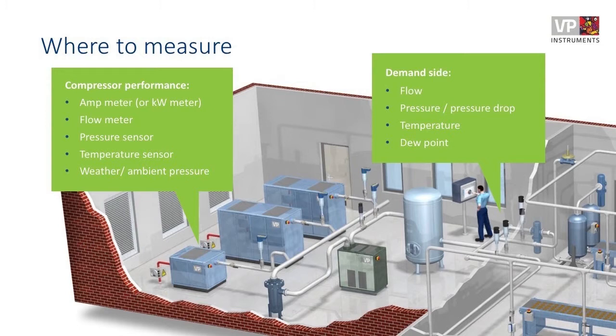And then dew point. If you have a critical application, you might want to monitor the dew point locally, so you don't have to waste, for example, your product. We had an example of a factory that produces things based on flour. If you have too much water in the pipes which transport the flour, in this case transported with air, then you might get fungus inside your product, which you don't want.